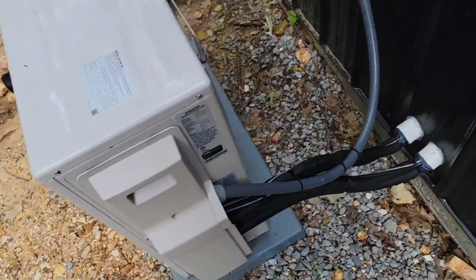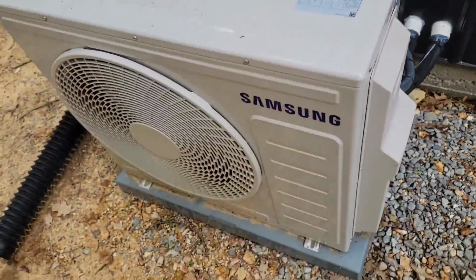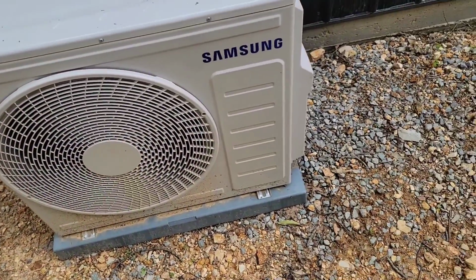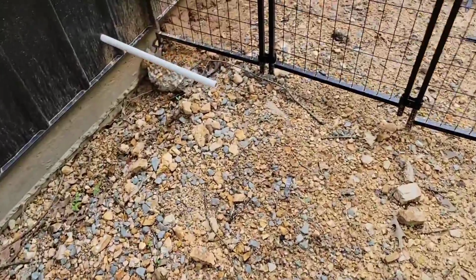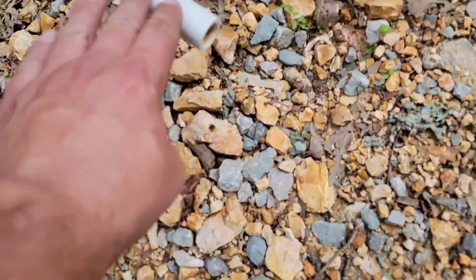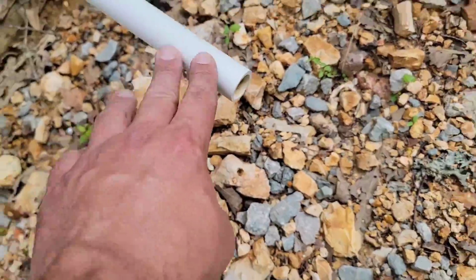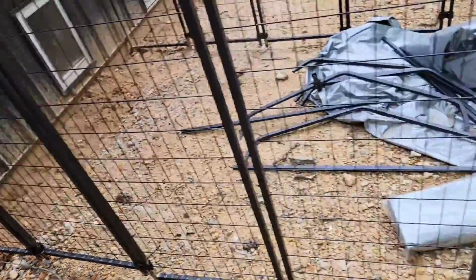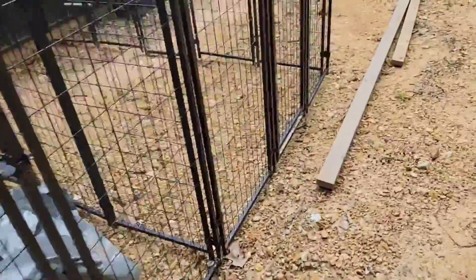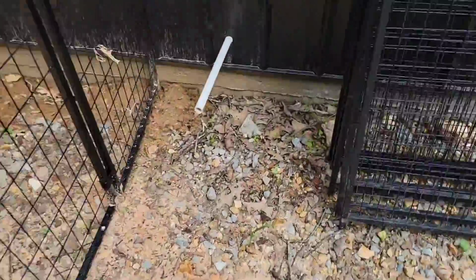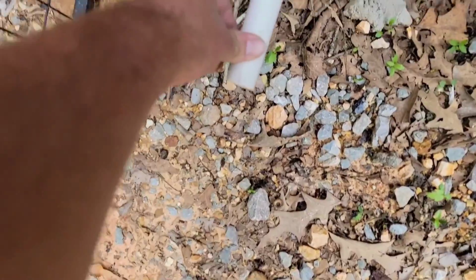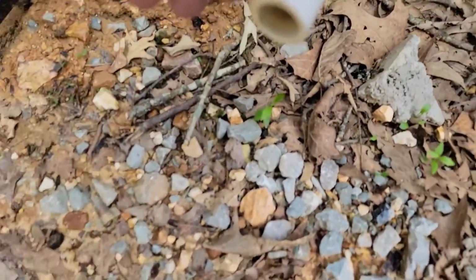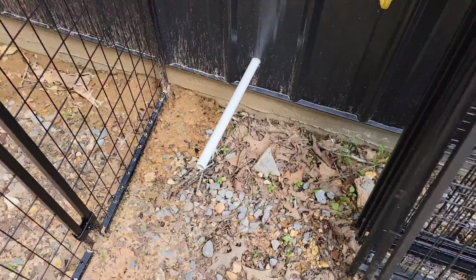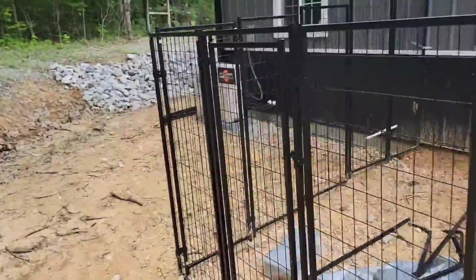The Samsung is pumping 100% on cooling. Wonder if we got any water. It's really important to check and make sure that everything drains. Make sure that that condensate pump inside for that air handler is draining. Nothing's pouring down the wall. Anything? Nothing yet. Hasn't been running very long, so that's okay.